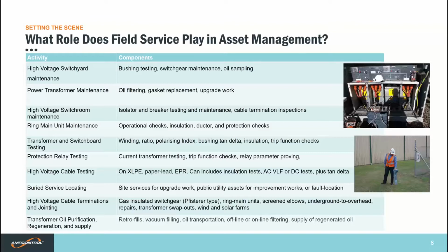Ring main unit maintenance, checking the operation of the RMU, doing insulation, ductor and protection checks on the switches, making sure everything works. Transformer and switchboard testing. Here we do the winding ratio, polarizing index. We can do bushing tan delta, insulation or trip function checks. Protection relay testing is a big one with the modern relays in place now. There can be current transformer testing, again trip function checks and relay parameter proving.